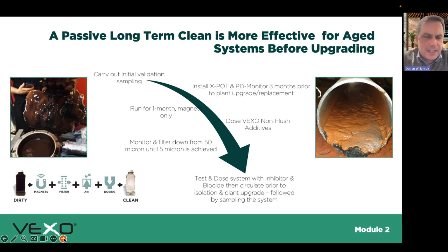You can see in the top left picture, that came out of a system over 25 years old at a university - that's magnetite and biofilm, with somebody holding a magnet grate. The picture on the right was the main primary header in an old school. Imagine doing a quick flush over a week before connecting your new equipment - even if you're fitting a plate heat exchanger to protect it, consider what's coming down the line into that nice new unit.